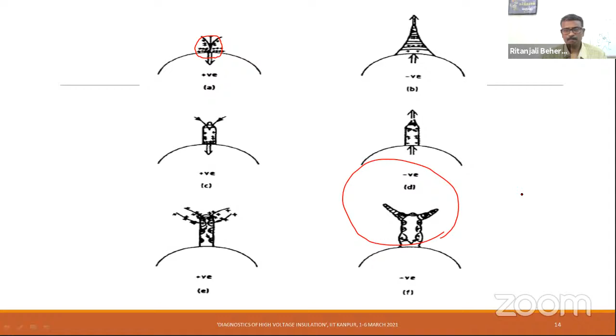Stages: inception stage and propagation stage. The cavity or small tube is formed at the high stress region, large enough to support PD, but may not be discerned. This is the initial stage, where things take place in the micro void which is very small, and the PD taking place will not be detected by the detector.